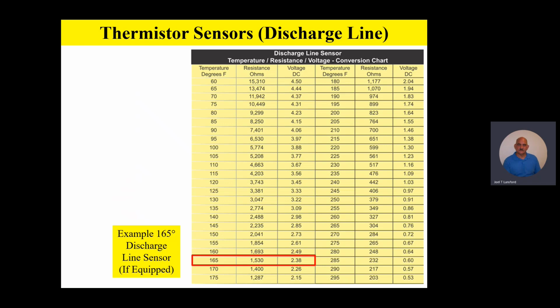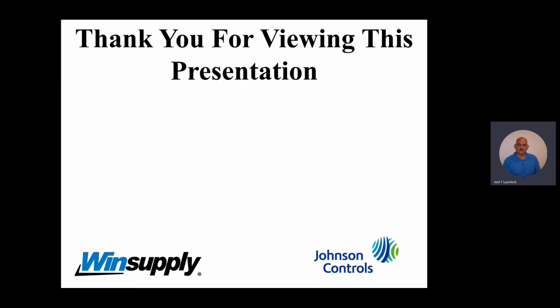When we go up to a defrost control and we suspect that it's not working right, or the sensors aren't working, instead of just replacing everything, let's take a few minutes and get in there and check those sensors and check the DC voltage and make sure we have 24 volts AC between C and R on the defrost control, and then start digging in and checking those sensors and be proactive about our testing procedures.